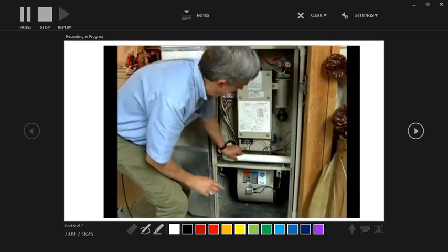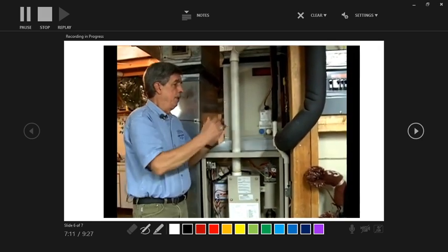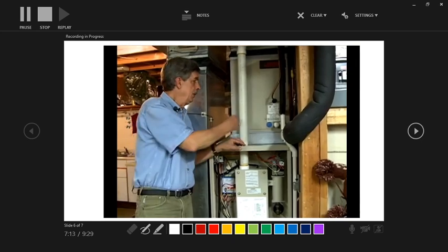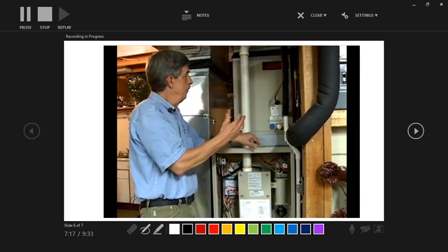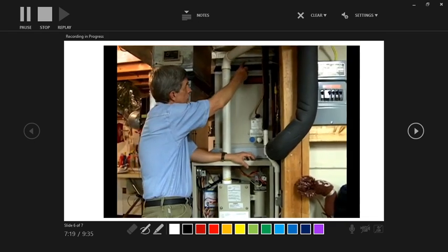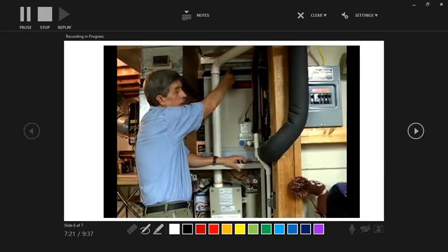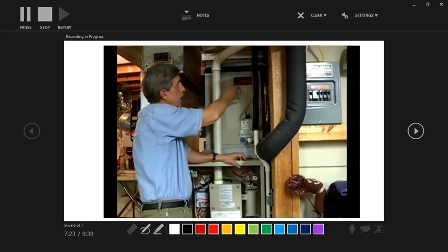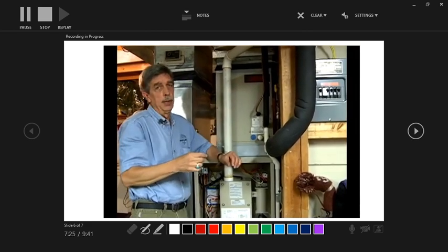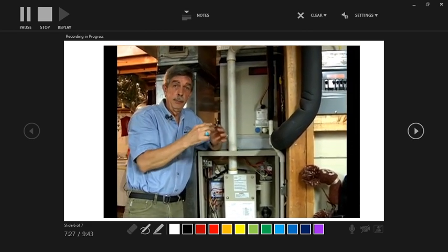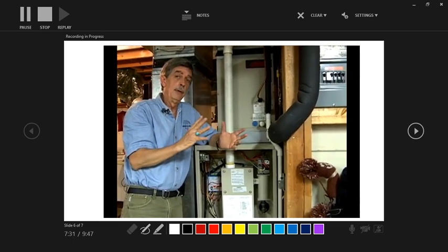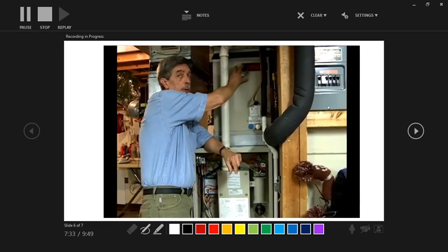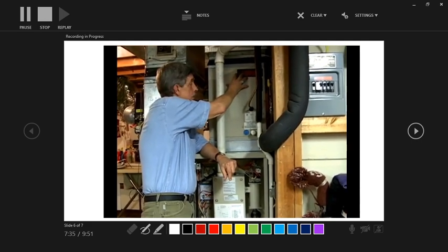Now, if we don't have enough refrigerant, if say there's been a leak and we turn the unit on, how do we know if this is occurring? Well, a surefire way of doing it is that a lot of times you'll find a small 1/8-inch diameter hole drilled right above the A coil. That's because a previous heating and cooling company has drilled that hole there to put in a simple probe thermometer, like a meat thermometer. You want to read about 55 degrees. 55 degrees above the coil is about maximum operating temperature.